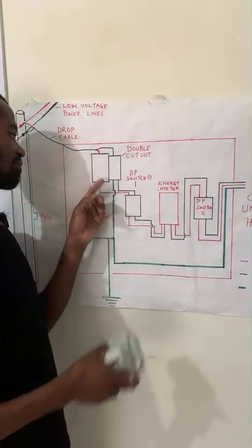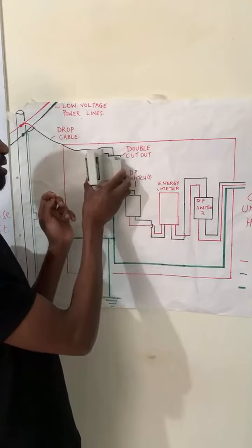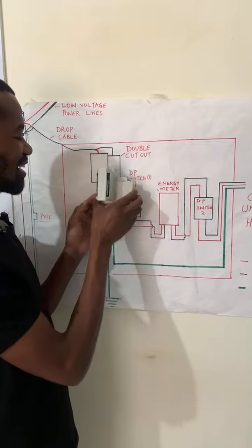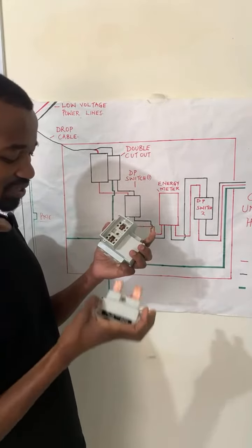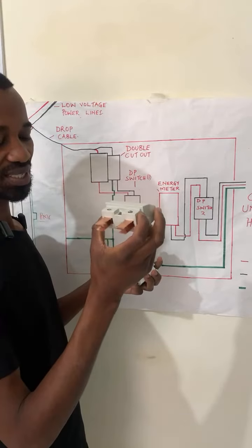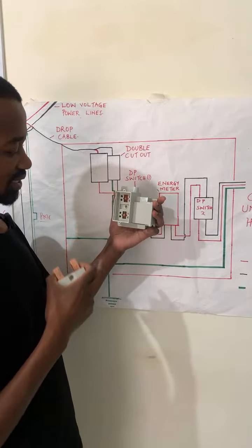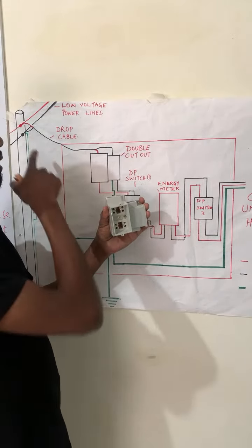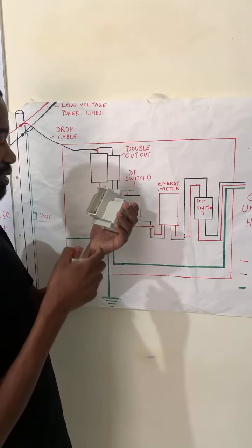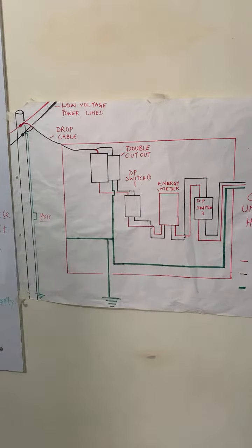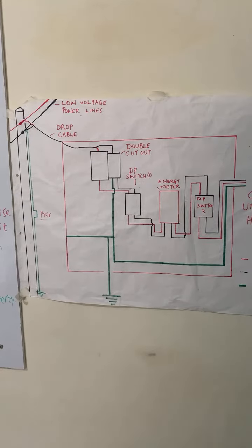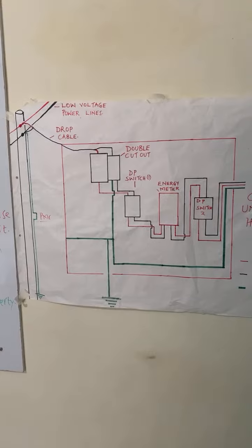So at this point, we will have this double cutout. I like using a double cutout because it's a two-in-one thing. It has a connection for the phase, hosting our fuse. It is an 80 ampere fuse for the phase connectivity that will be flowing here. So once the drop cable comes from the pole, it will get into this particular point, and then we'll have to bond the earth as well as the neutral together. And someone called me and asked me, my good friend, how can we connect that? And today I'm going to elaborate exactly that.